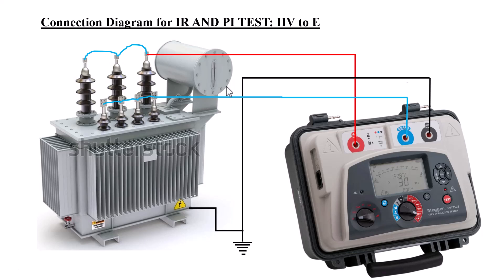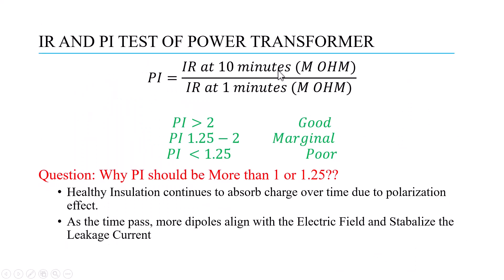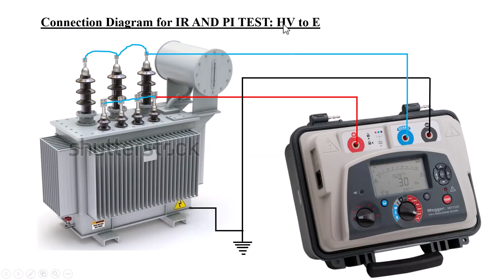For high voltage to earth, the positive lead is connected to the high voltage winding with all three phases shorted, and the negative lead is connected to earth. The guard is now connected to the low voltage winding, because the low voltage winding may disturb the HV-to-earth test results. The guard is used to protect the results and keep them accurate.